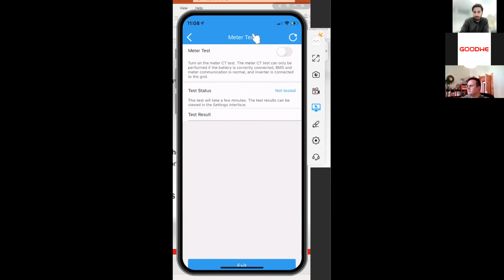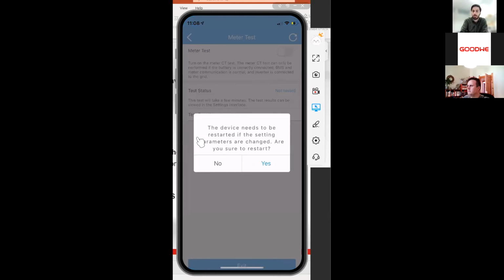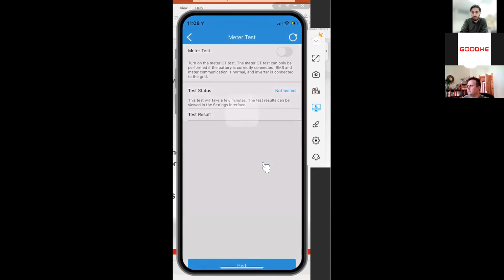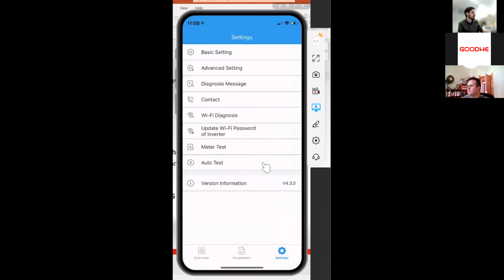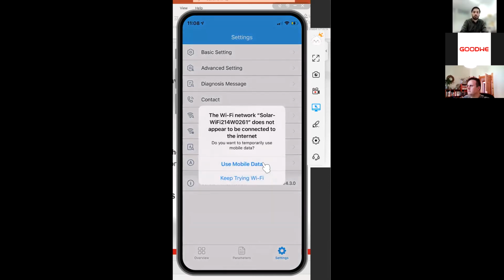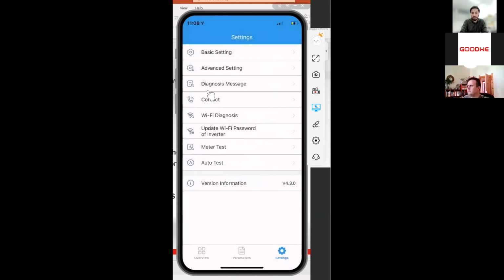Then all is good. So I haven't connected the meter now to this, where it's connected to the inverter, but the CTs are not connected, so the meter test will anyways not work. We skip this now, we press on exit, and then we have gone through all the setups. So now the device needs to restart. We press on yes, and it will take a few minutes. You can also then usually see on the inverter that it blinks, and then you will come back here to the main screen.